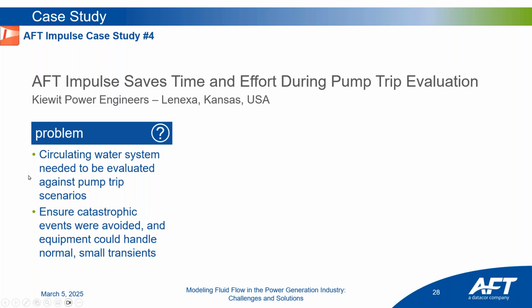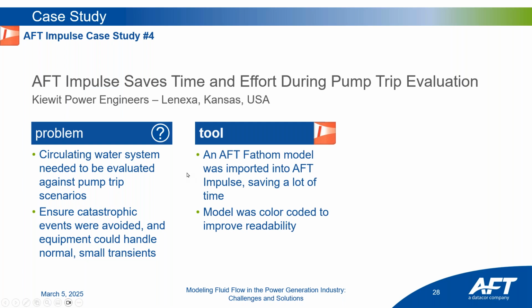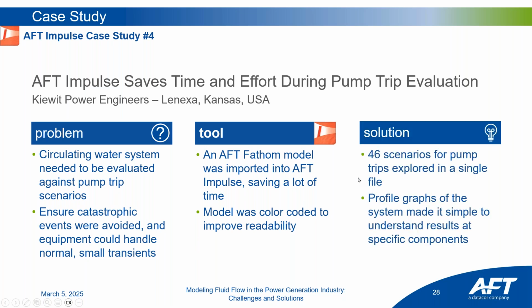Safe shutdown, safe startup operations, pressure extremes, and protecting especially the high expensive equipment, which were the condensers, okay? They'd ensure catastrophic events were avoided, equipment could handle normal and small transients, okay? First, what they did is they had an AFT Fathom model that existed of this cooling water system, a typical Fathom model. And then they imported that rather than build from scratch, and they were able to start their Impulse model from a Fathom model, which saved them a lot of time and effort. The model was color-coded to improve readability. The model had 46 scenarios for pump trips and pump startups, and it's all in a single model file.